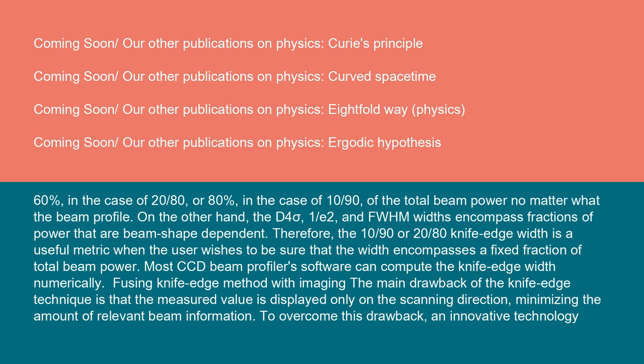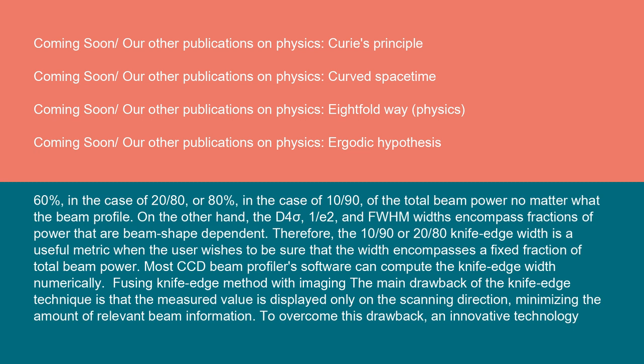Fusing knife edge method with imaging: The main drawback of the knife edge technique is that the measured value is displayed only on the scanning direction, minimizing the amount of relevant beam information. To overcome this drawback, an innovative technology offered commercially allows multiple directions beam scanning to create an image-like beam representation. By mechanically moving the knife edge across the beam, the amount of energy impinging the detector area is determined by the obstruction. The profile is then measured from the knife edge velocity and its relation to the detector's energy reading. Unlike other systems, a unique scanning technique uses several different oriented knife edges to sweep across the beam.